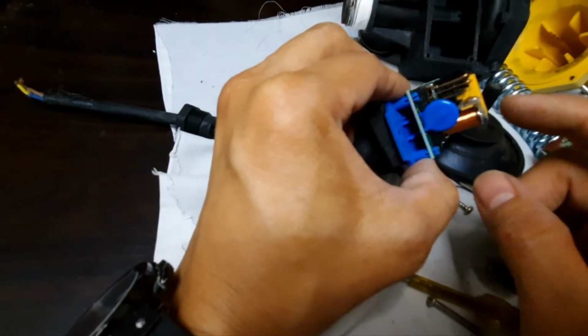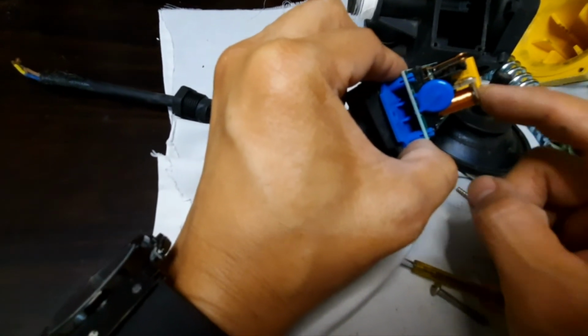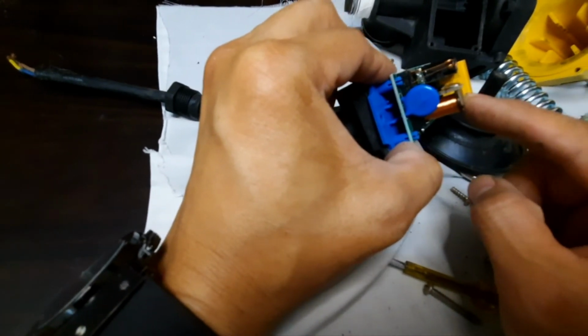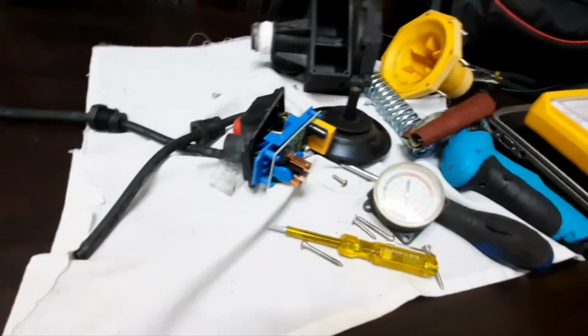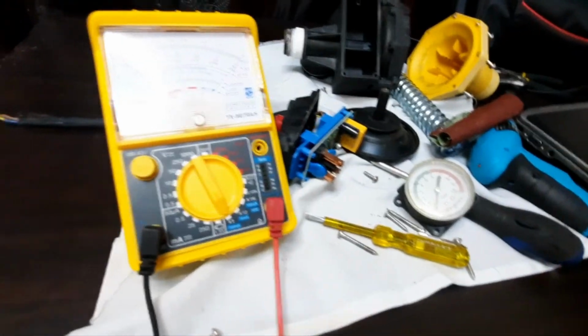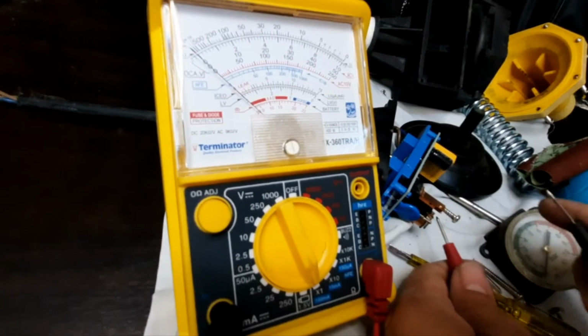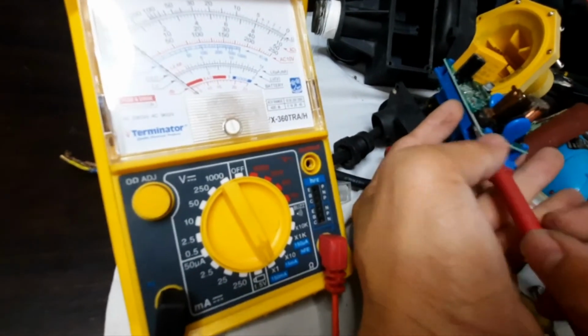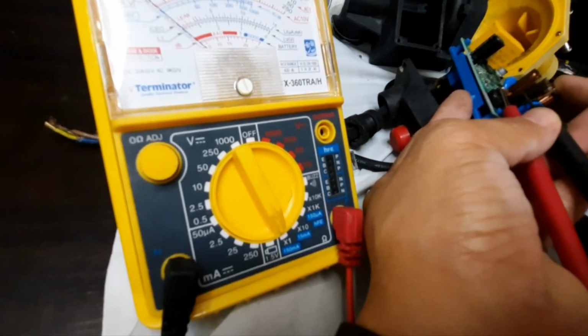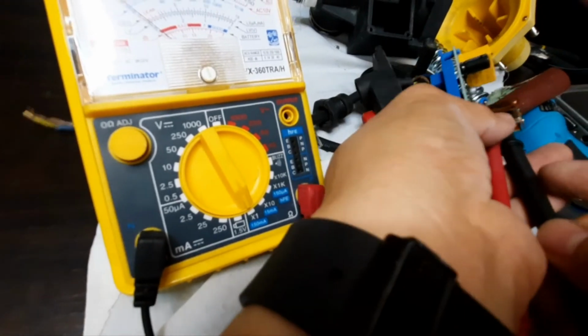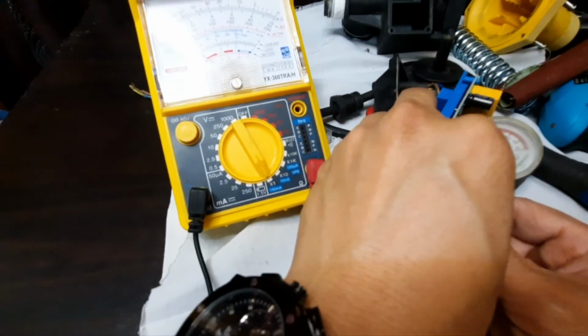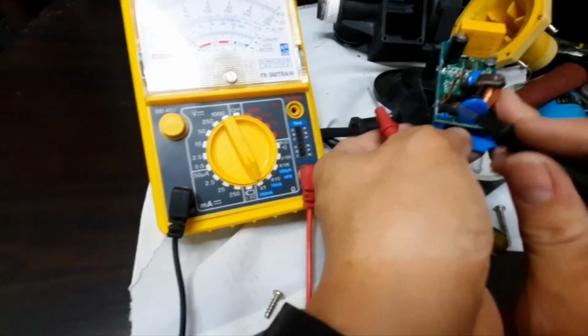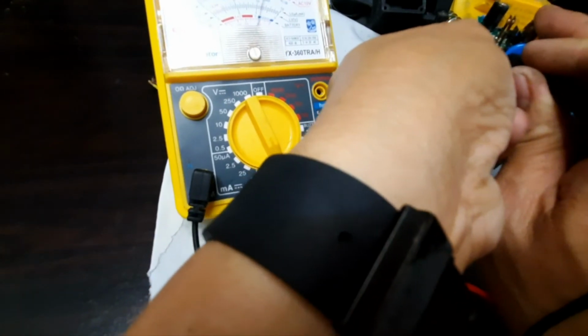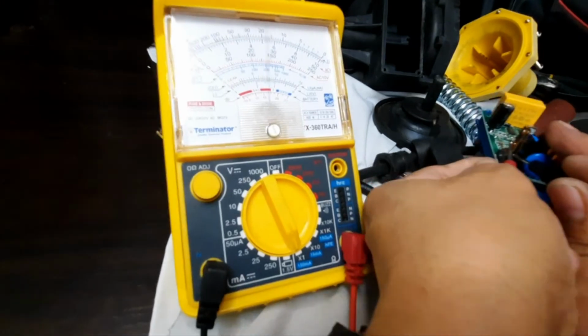Okay, so this is acting like this. So if it is magnetized, then the contact becomes NC, or normally closed. We can check using our multimeter if the contact is okay or not. Okay, so we're going to push the relay like this. And so as you see here, if I push this, it is getting contact. Then open, I push.